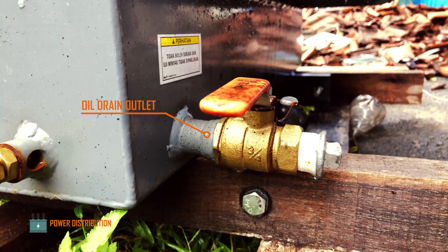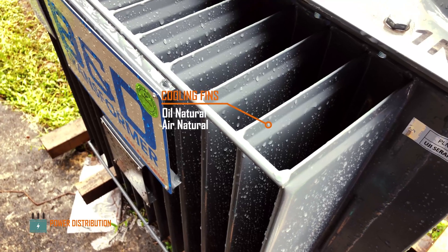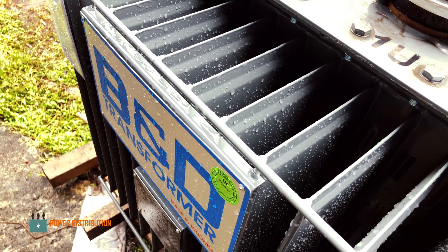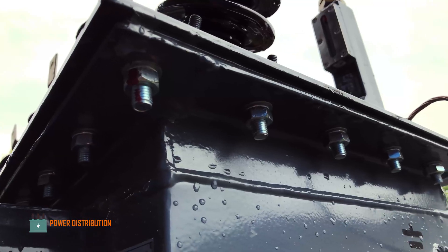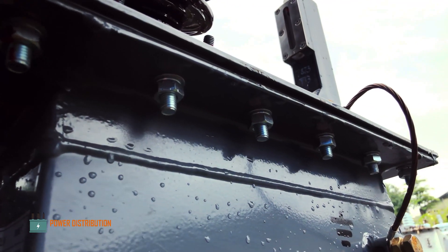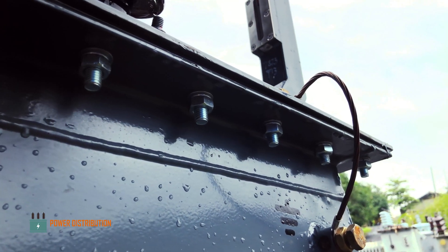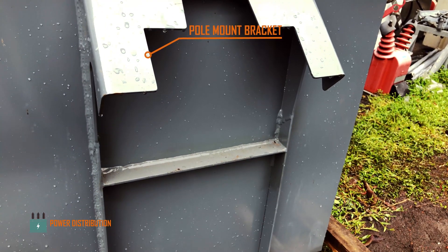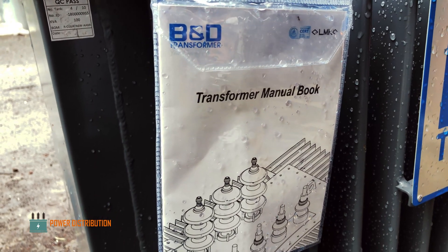This transformer utilizes a passive cooling system using cooling fins — air natural and oil natural — along with another seal gasket and mounting bolts. There is also a lifting lug for transportation purposes, a pole mount bracket, and a manual book for installation and maintenance.